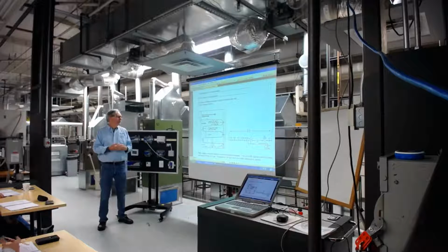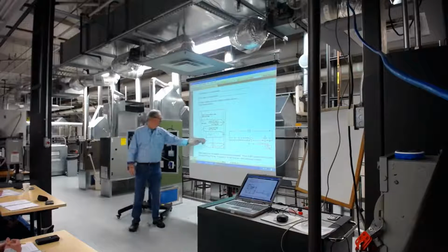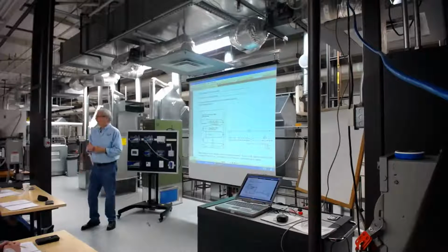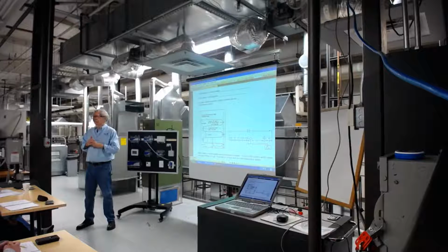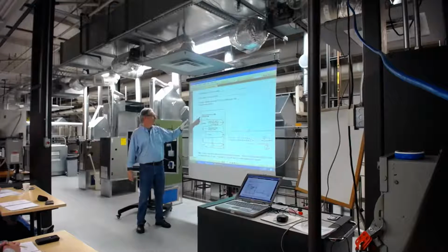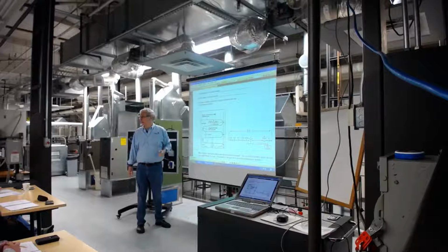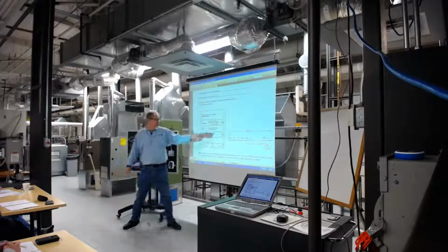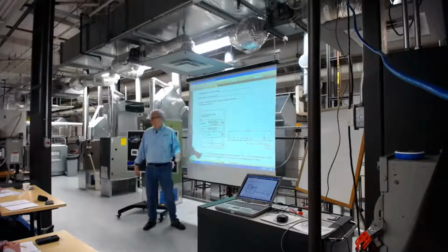So what will happen is, as it gets colder, you're getting a change in temperature. What happens to the refrigerant is it changes phase, which is what it's supposed to do. And that in turn will change the pressure, which will then open up certain contacts. You get normally open and normally closed. Typically, they use normally closed contacts in series with the starter right here.